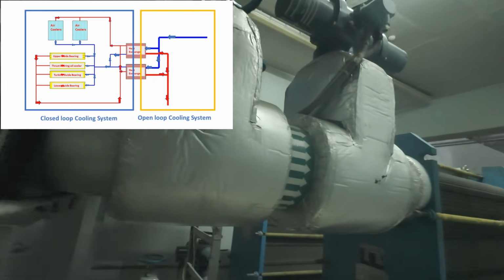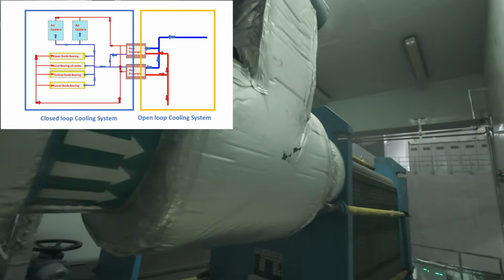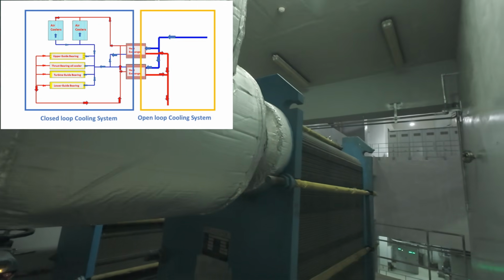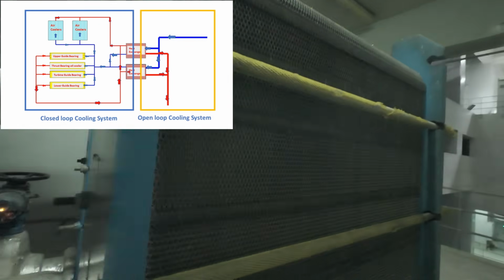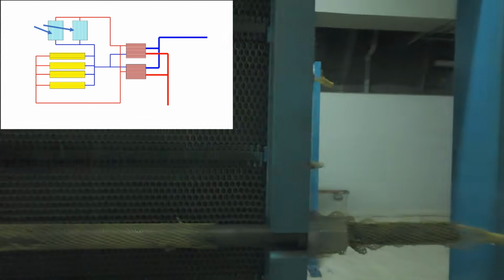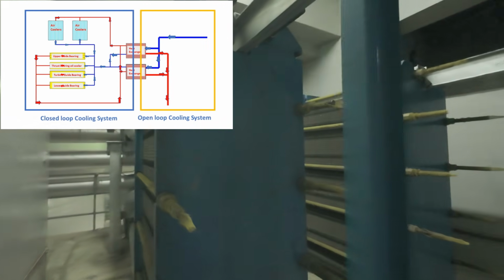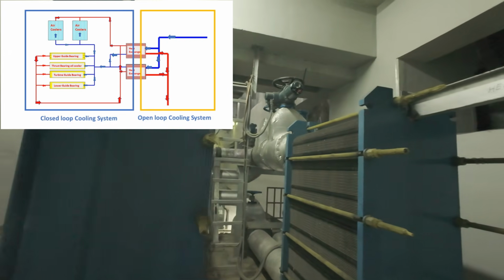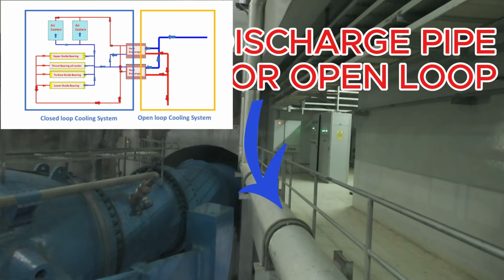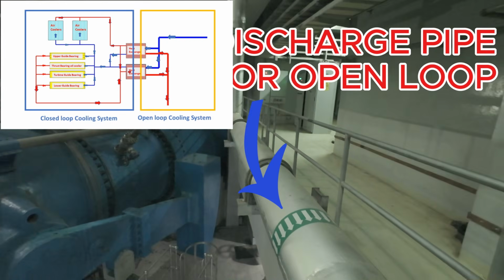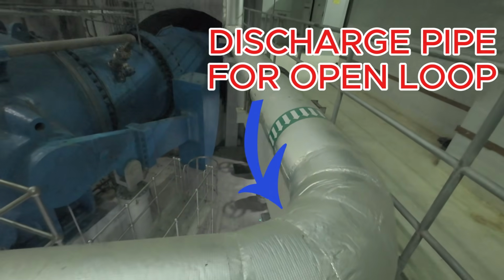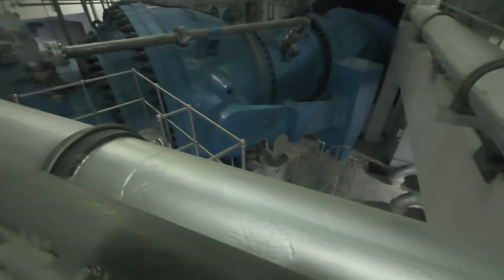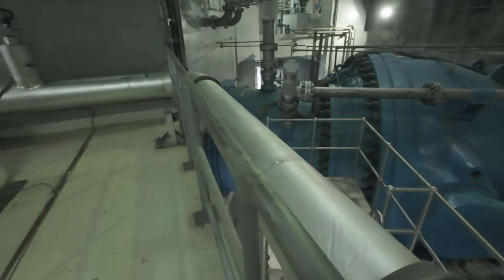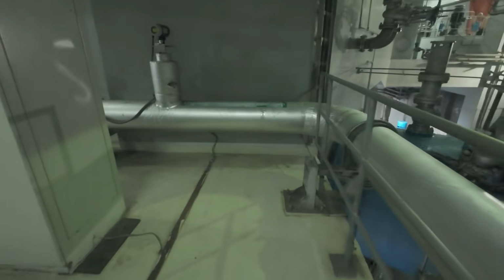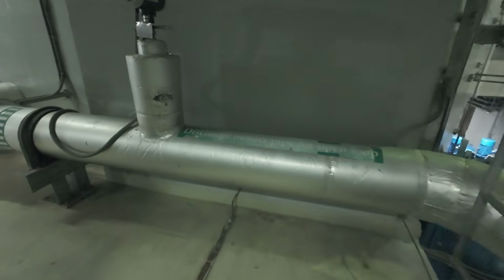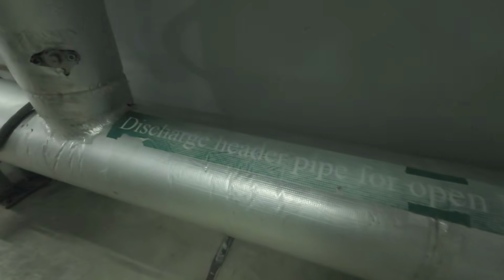The closed loop water now flows towards the most critical parts of the hydropower unit. First, the generator air cooler. Inside the generator, electrical losses create huge heat. Cooling water removes heat from circulating generator air to protect stator insulation. Next, the thrust bearing oil cooler. This bearing carries the entire vertical weight of the turbine generator shaft, and that load can reach hundreds of tons. Without cooling, bearing oil temperature would rise rapidly.